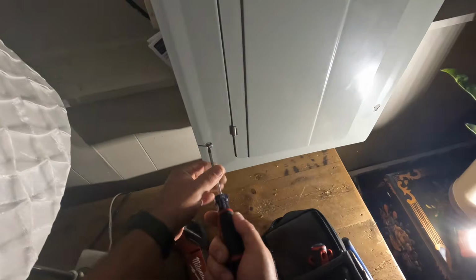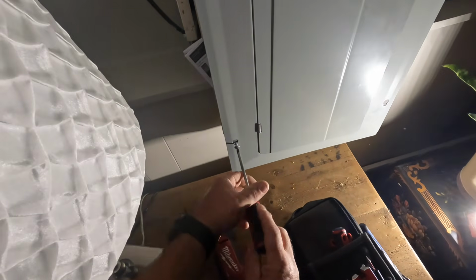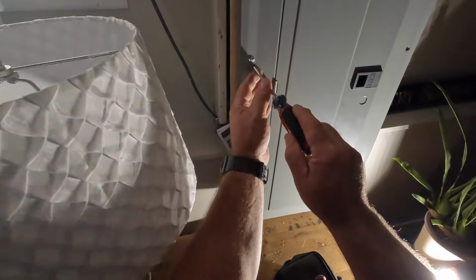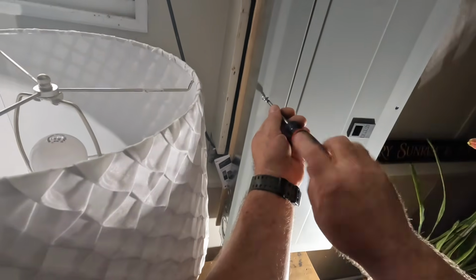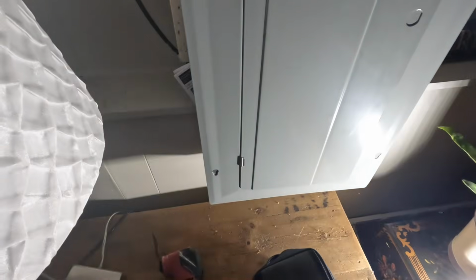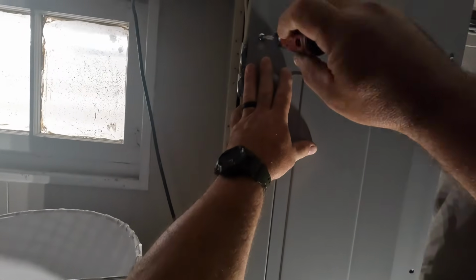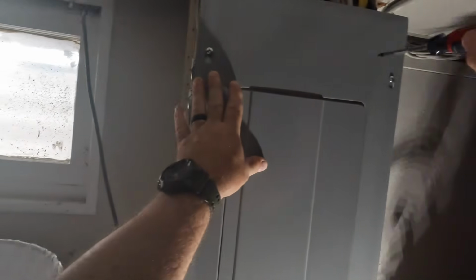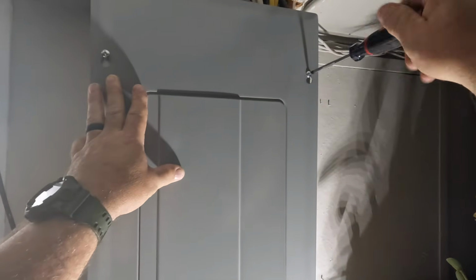So in order to accomplish wiring this transfer switch, I need to take out the feed that comes from the meter into the main breaker inside this panel, because now the main breaker in this panel is actually going to become what's known as a main lug only panel. Even though we're keeping the main circuit breaker in there, it's technically not the main breaker.